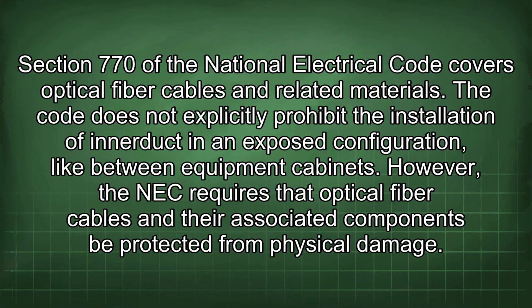Section 770 of the National Electrical Code covers optical fiber cables and related materials. The code does not explicitly prohibit the installation of Innerduct in an exposed configuration like between equipment cabinets. However, the NEC requires that optical fiber cables and their associated components be protected from physical damage.